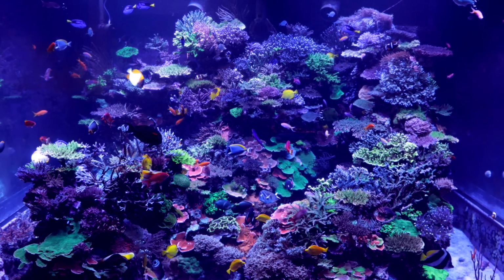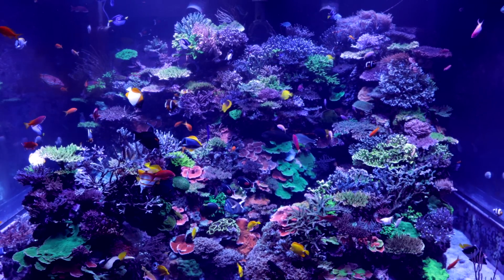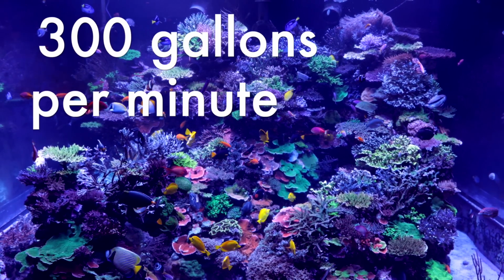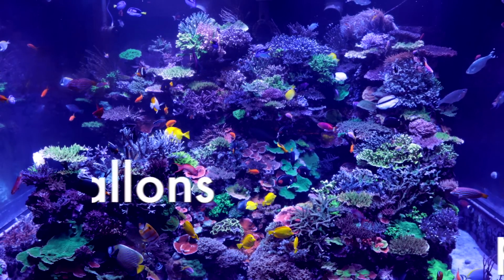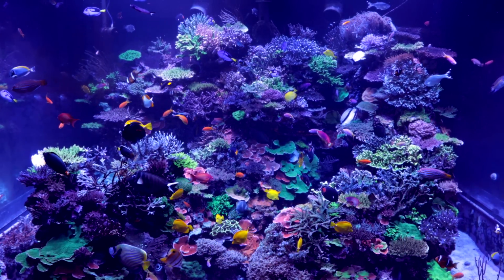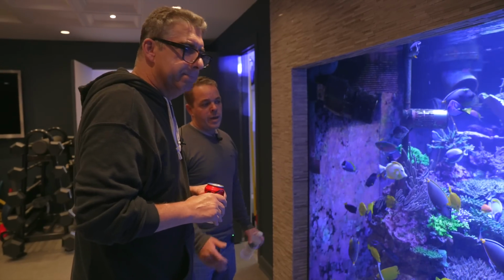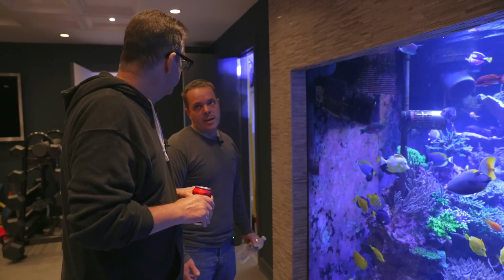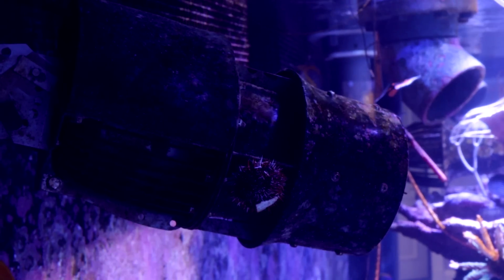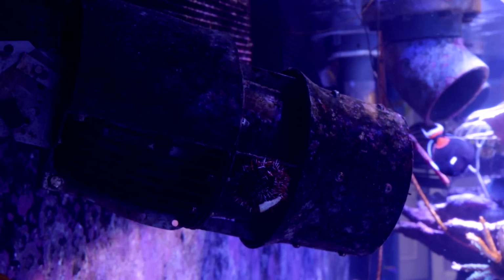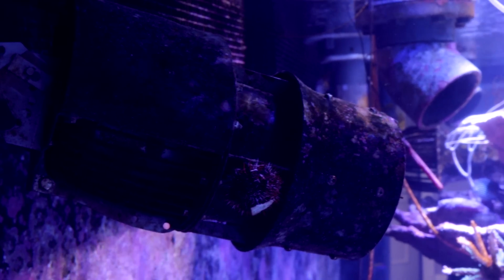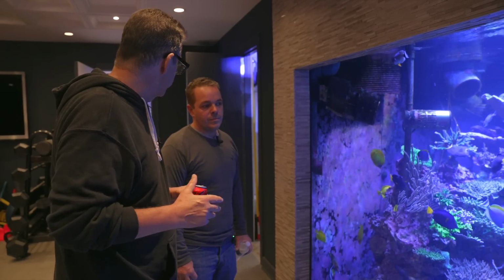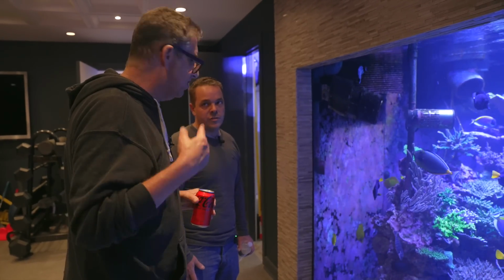What's the gallons per minute going through there? On the closed loop, it's approximately 300 gallons a minute. On the open system that runs down to the sump, right now we're flowing about 600 gallons a minute, with capabilities of flowing higher than that, but we feel that this has been our sweet spot. And if you add in the sumps and stuff like that, you're talking about 1,100, 1,200 gallons per minute through the system.